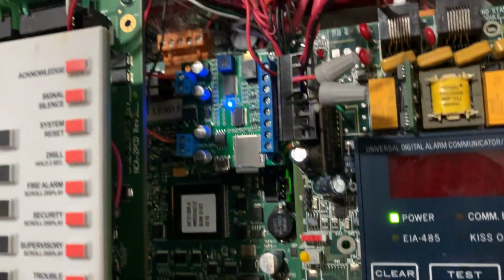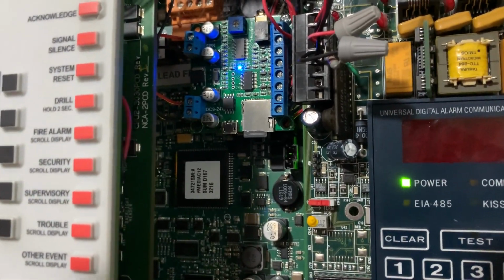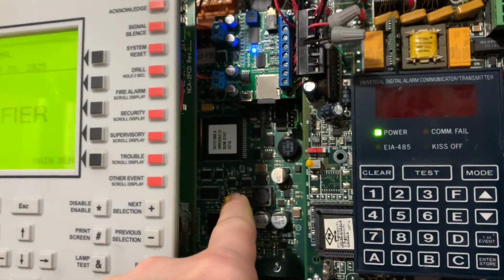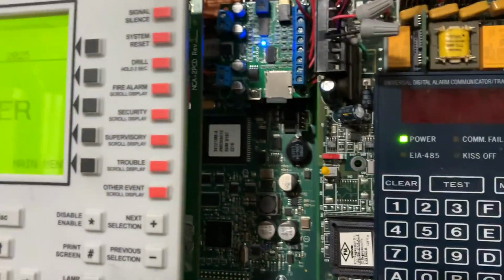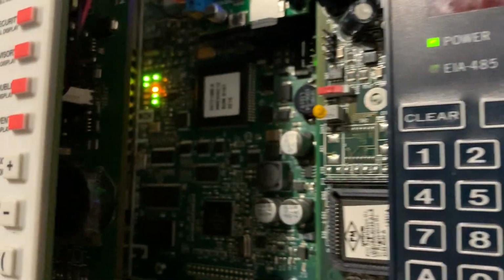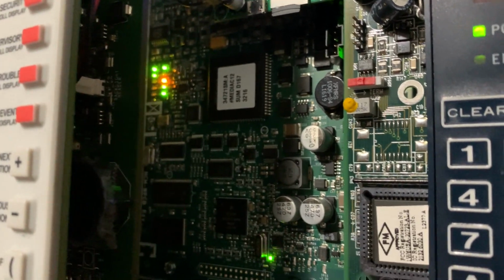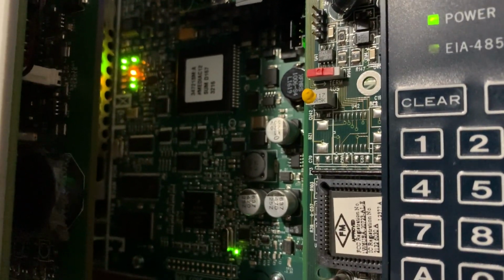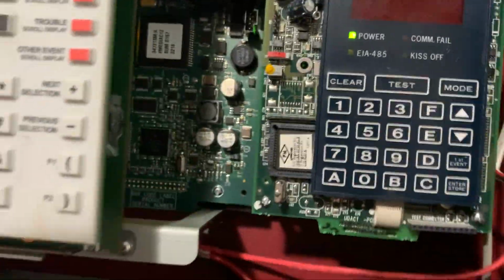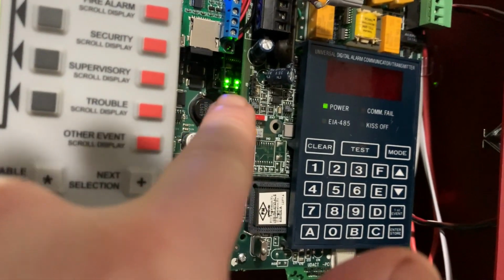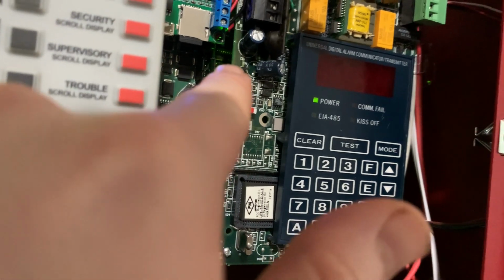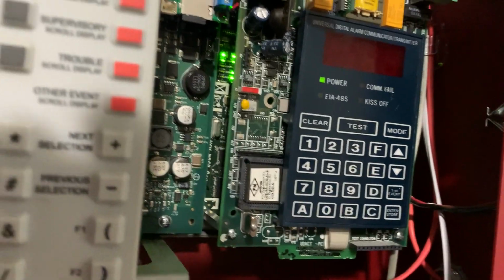Inside here as well. And if you look in the back of there, we got an NCM-W, and the MP3 board is right behind it. See, this NCM right here is for the 640, and if you look back there, you notice that the lights on the NCM are on. That shows that the NCM-W is working. And I also have another NCM behind the UDACT, but you see there's no yellow lights lit up on this NCM.